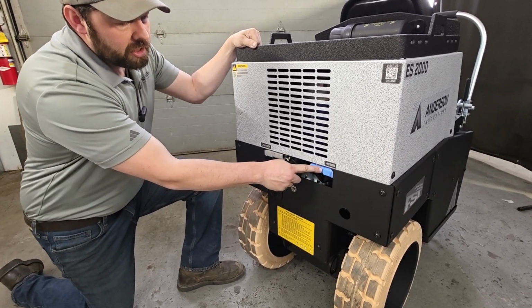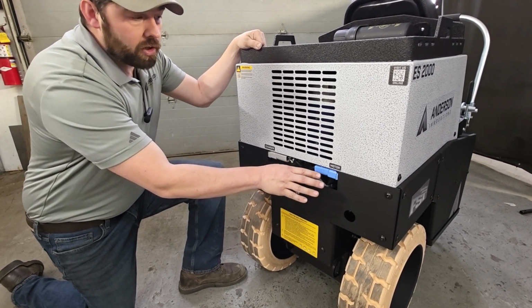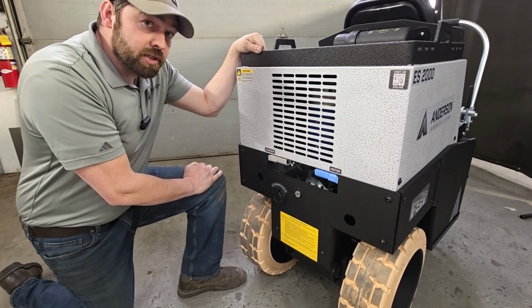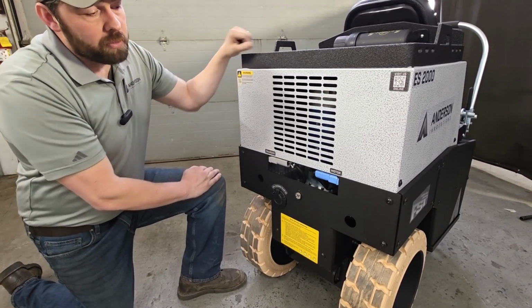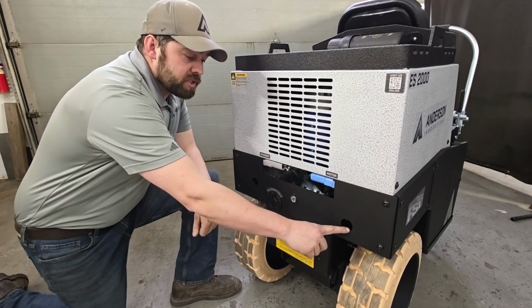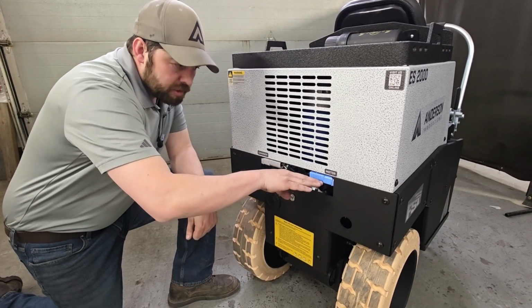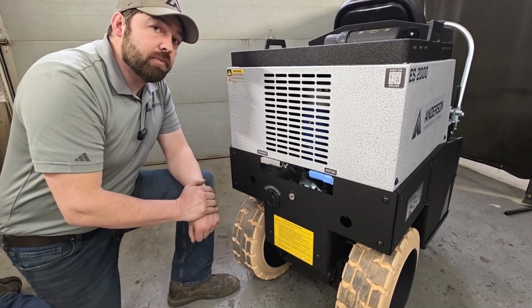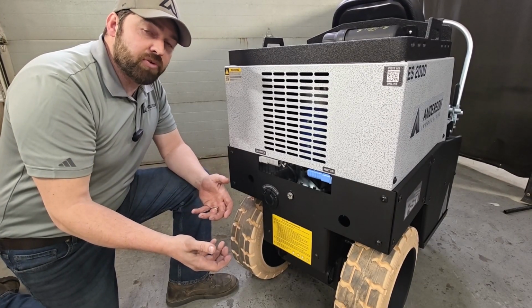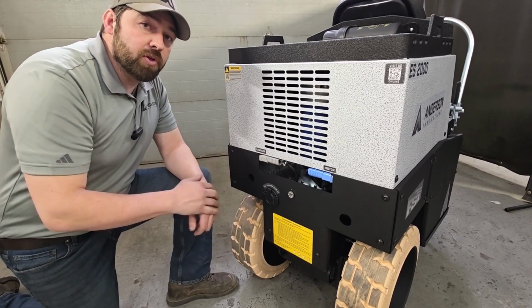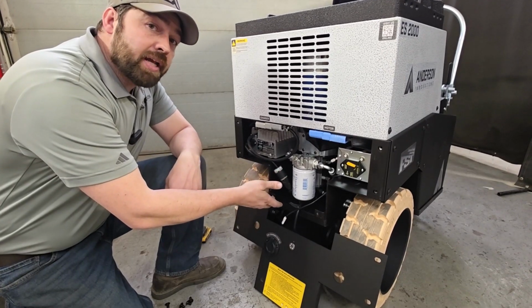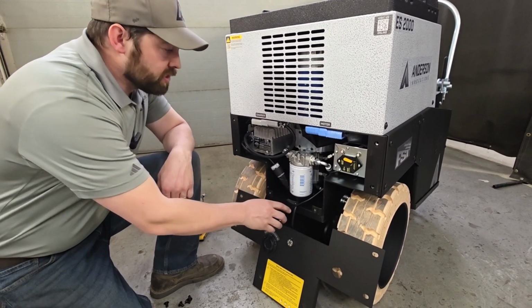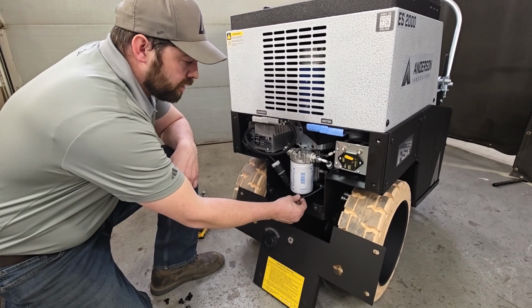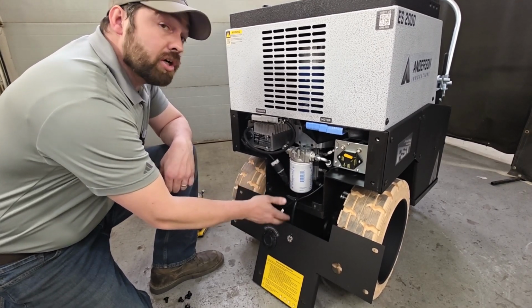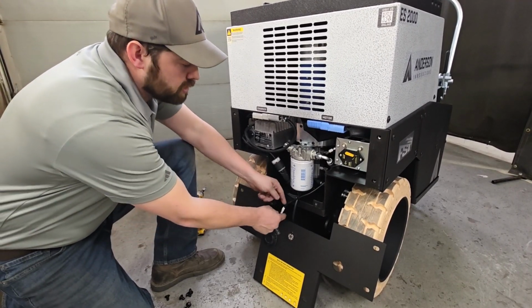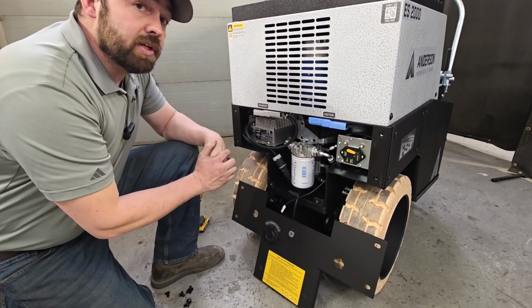If this connection is installed and is clean, there are a number of circuit breakers on the back of the machine. You'll be able to see these breakers through this access hole, as well as through the opening in the back of the machine. We're going to remove this panel just to provide a more open view of those circuit breakers. If you remove the back panel on the machine, be careful as there are two cords, the backup light and the charger connection, which are attached to the rear panel. Both of these can be removed by plugs if needed.